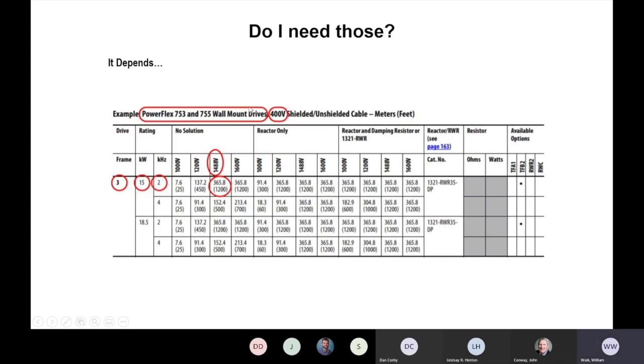So I just have a couple of our VFDs highlighted here, the 753 and the 755, rated at 400 volts. If we're using an inverter rated motor at 1488 volts insulation rating, we have no solution on this, and we're not using a line reactor or anything like that, depending on your power rating, we have a maximum of 1,200 feet when it comes to this. And we have an entire matrix too on whether or not you're going to require line reactors on this.